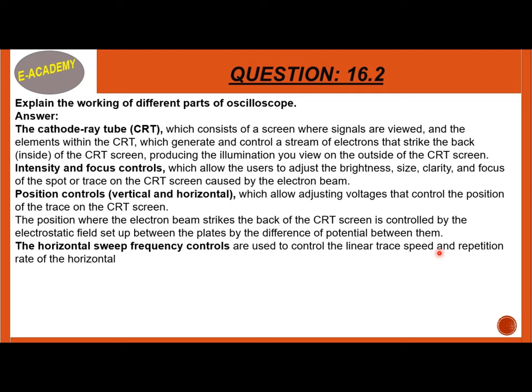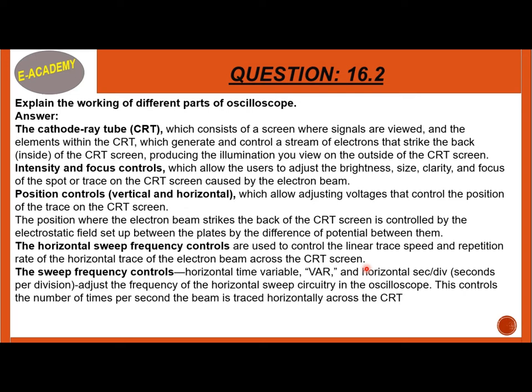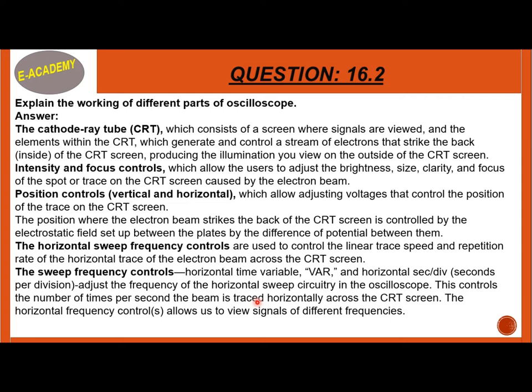Next is the horizontal sweep frequency control. These are used to control the linear trace speed and repetition rate of the horizontal trace. The horizontal time variable and horizontal seconds-per-division adjust the frequency of the horizontal sweep circuit in the oscilloscope, controlling the number of times per second the beam is traced horizontally across the CRT screen.